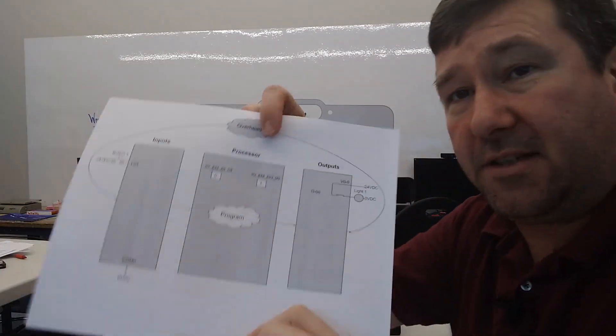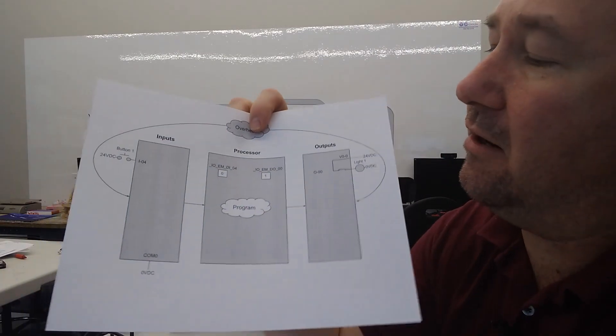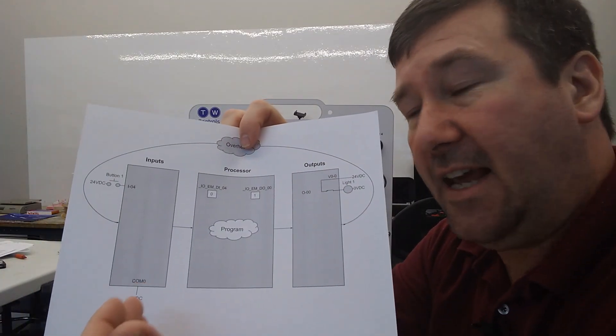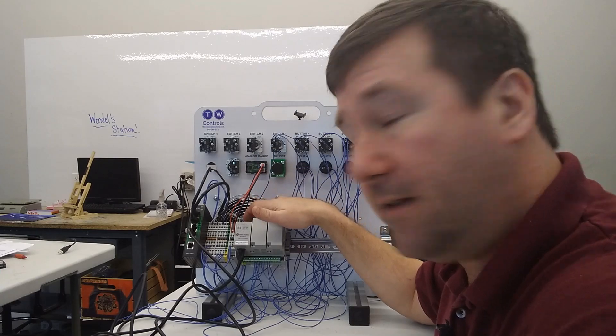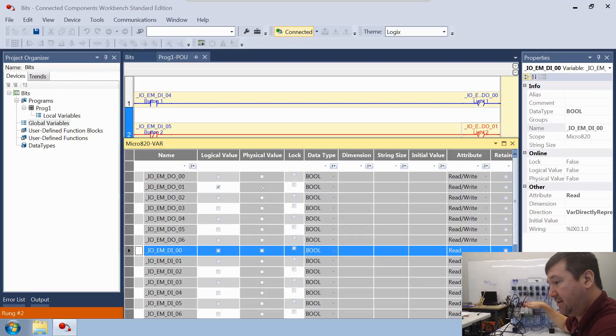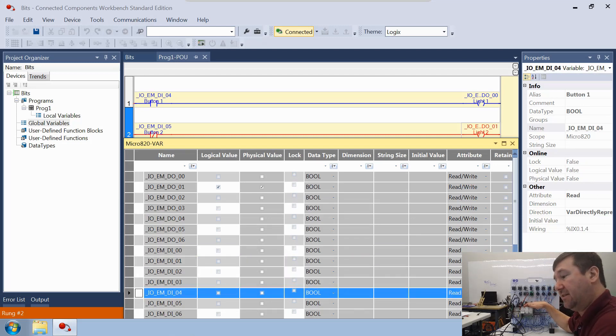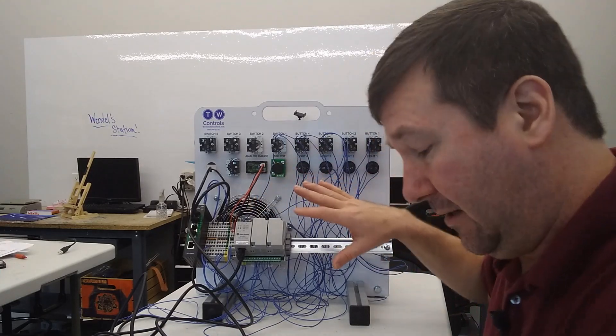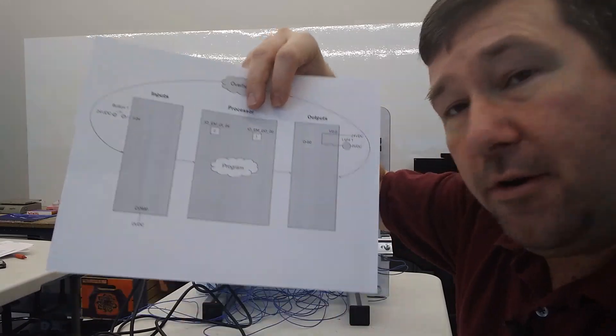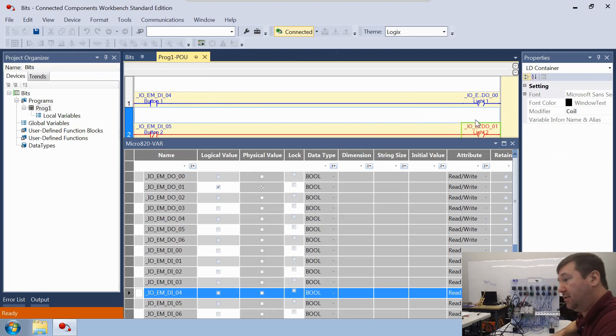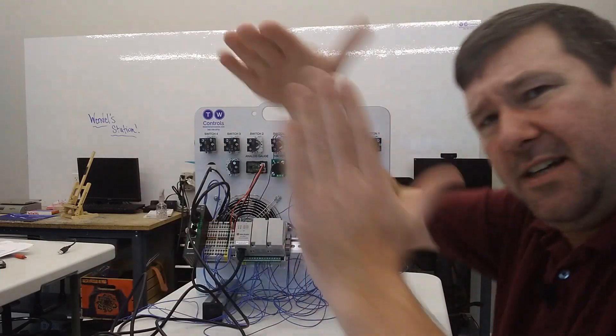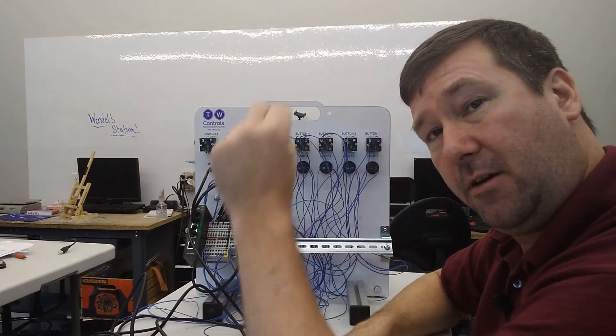Let's put all this together with our scan worksheet from the previous video. The first thing a PLC is going to do is scan its inputs and update the global variable sheet. It's going to look at Input 0 and say, do I have current? It goes all the way through, reading each physical input and updating the global variable. Then it's going to execute its program, starting at rung 1, executing from left to right, then rung 2, and so on. It doesn't do them all at the same time.